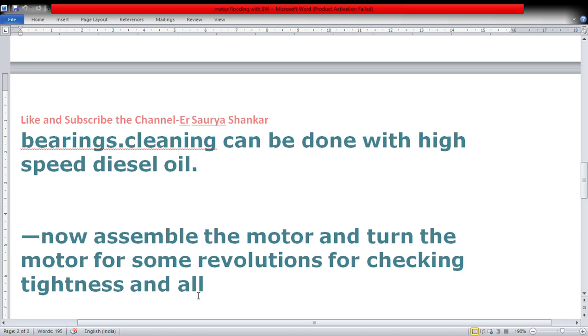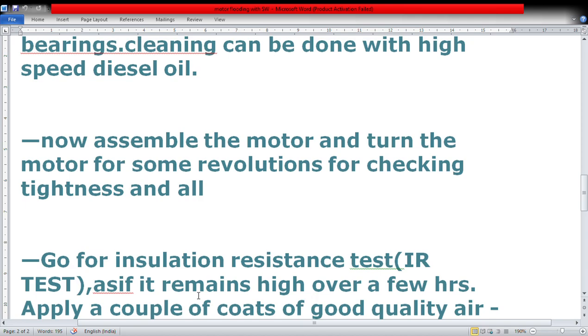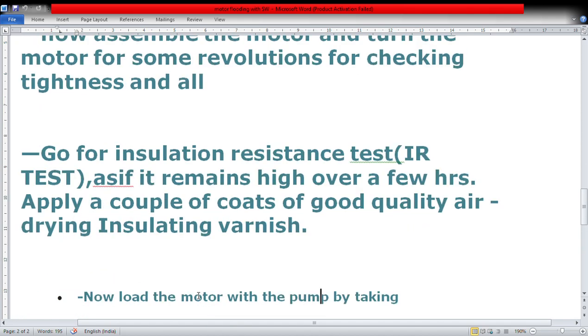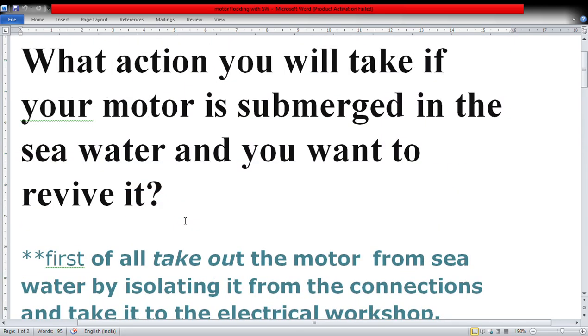Assemble the motor and turn it for some revolutions to check tightness. Go for insulation resistance IR test. If it remains high over a few hours, apply a couple of coats of good quality air-drying insulating varnish. Then the motor with the pump is tested by taking it on to the load.